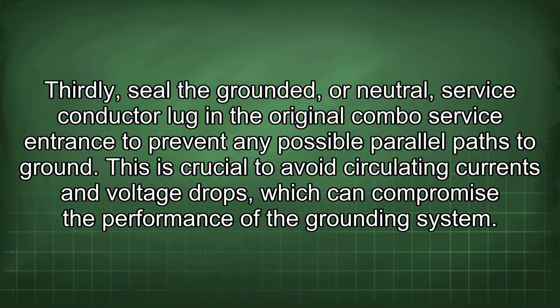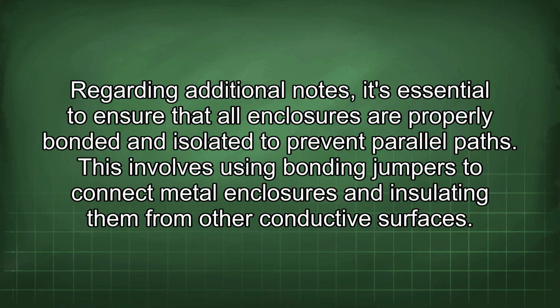Thirdly, seal the grounded, or neutral, service conductor lug in the original combo service entrance to prevent any possible parallel paths to ground. This is crucial to avoid circulating currents and voltage drops, which can compromise the performance of the grounding system. Regarding additional notes, it's essential to ensure that all enclosures are properly bonded and isolated to prevent parallel paths. This involves using bonding jumpers to connect metal enclosures and insulating them from other conductive surfaces.